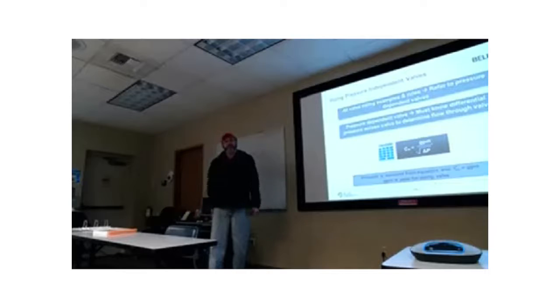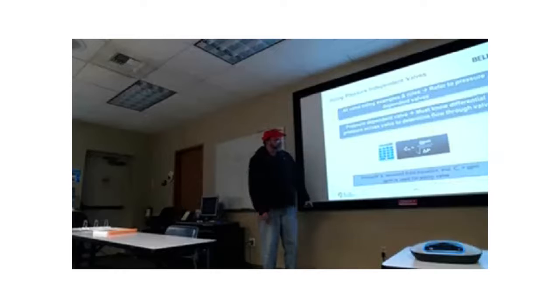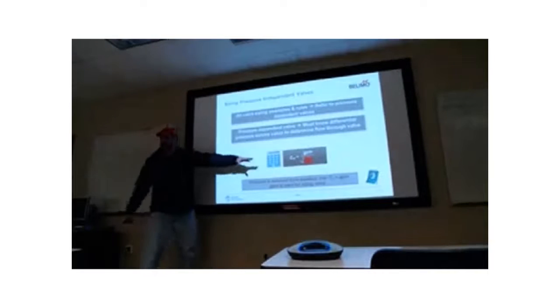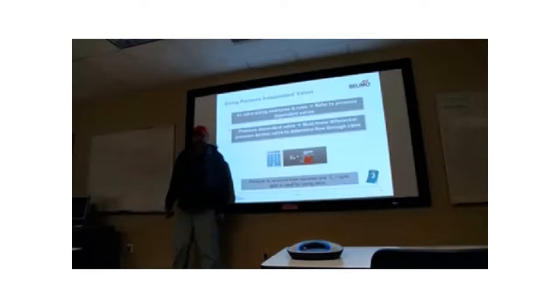So that's just one. If everybody tells you, yeah, we've got pressure independent valves, well, check, because you may have basically just a balancing valve and not a true pressure independent valve. Two different things. I don't want to put too much math on you here, but here's our formula that we used before. When we take the pressure out of it, so now we have no differential pressure to design to, the Cv is essentially equal to the flow rate, so it makes it all really easy now.